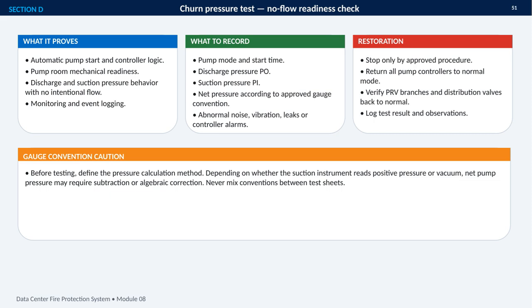Before testing, the team must define how net pressure will be calculated, because a suction instrument may show positive pressure or vacuum. That can change whether pressure is subtracted directly or corrected algebraically. Never mix conventions between test sheets. Finally, stopping must follow the approved procedure. Controllers should return to normal mode, PRV branches and distribution valves must be restored, and the complete result, including observations, should be logged.